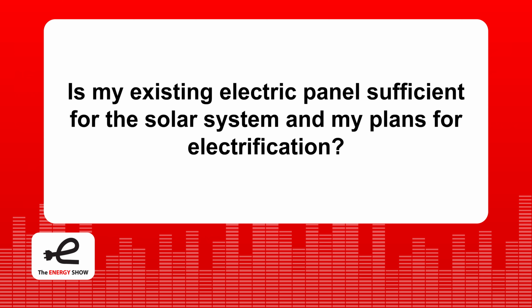The National Electric Code requires that your maximum inverter output be no more than 20% of your electrical panel size. In practice, if you have a 100 amp panel, common on small or old houses and condos, you can usually put in a 3.8 kilowatt inverter. A 125 amp panel, typical of older homes like in my neighborhood, works with about a 5,000 watt inverter. A 200 amp panel, standard on most new homes (with bigger homes now getting 400 amp panels), usually works with a 7.6 kilowatt inverter.